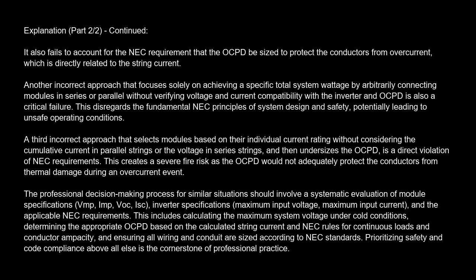The professional decision-making process for similar situations should involve a systematic evaluation of module specifications, VMP, IMP, VOC, ISC, inverter specifications, maximum input voltage, maximum input current, and the applicable NEC requirements. This includes calculating the maximum system voltage under cold conditions, determining the appropriate OCPD based on the calculated string current and NEC rules for continuous loads and conductor ampacity, and ensuring all wiring and conduit are sized according to NEC standards. Prioritizing safety and code compliance above all else is the cornerstone of professional practice.